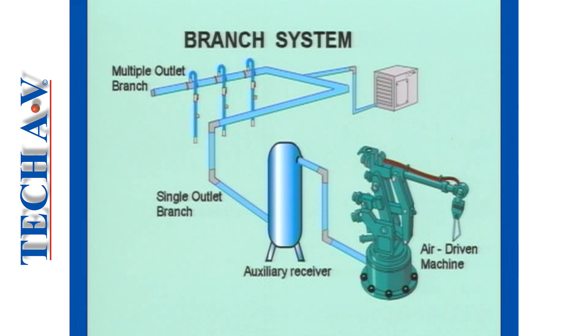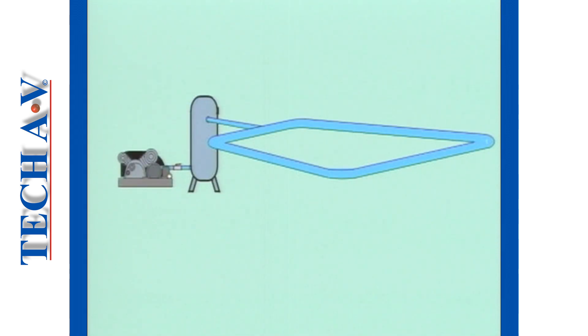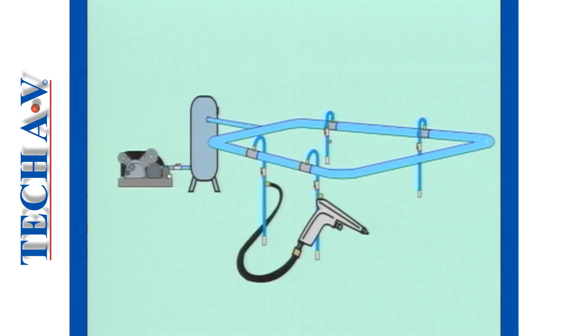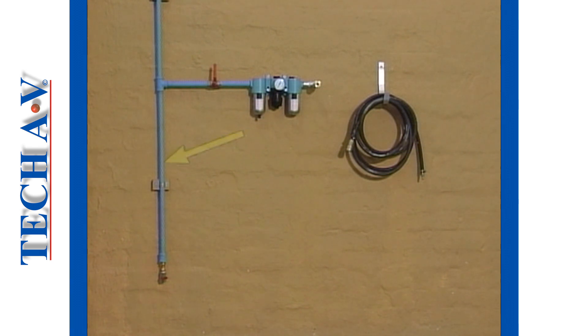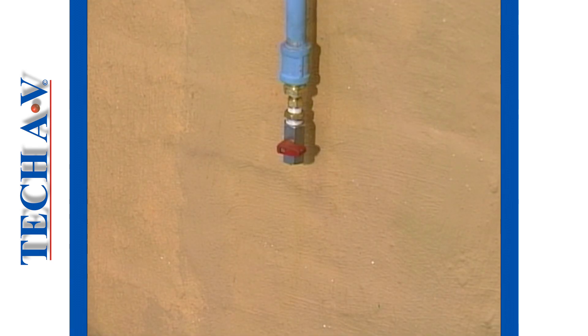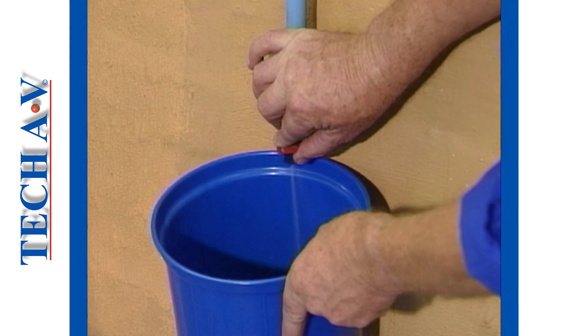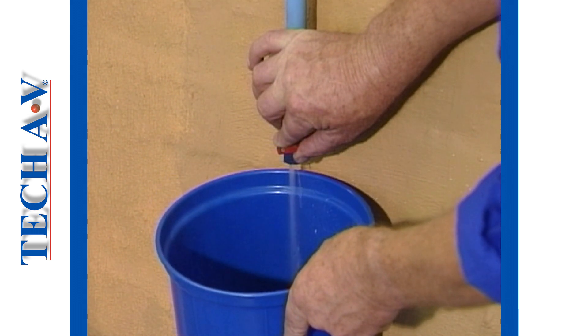Branch lines often feed into an auxiliary receiver, designed to supply a particular machine or section of the plant. At various locations along the air main, you will find user points, or outlets, into which working devices may be connected. In a properly designed system, a user point is fed off a drop leg. The lower section of a drop leg acts as a water trap. A drain cock, or valve, allows for water to be drained off when necessary.